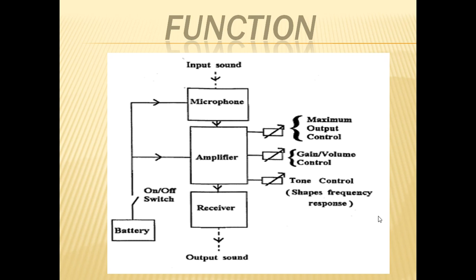Now the functions. This is commonly a diagram of how hearing aids function. Sound waves enter the hearing aid through the microphone. The microphone converts the sound waves into an electrical signal. The amplifier increases the strength of the electrical signal. A smaller loudspeaker called the receiver functions to convert the amplified signal back into sound waves. From the receiver, the signal is channeled into the ear canal either through a small tube or ear mold. A battery is required to power the hearing aid and enable the amplification process.